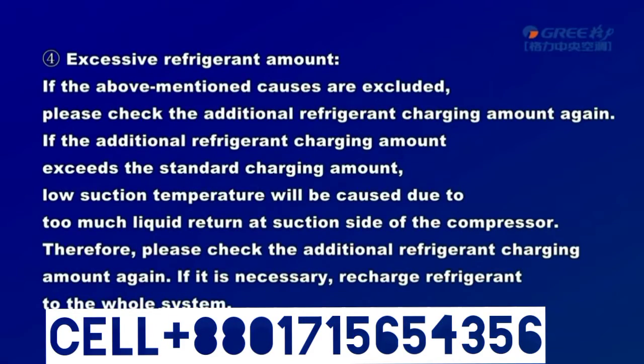4. Excessive refrigerant amount. If the above-mentioned causes are excluded, please check the additional refrigerant charging amount again. If the additional refrigerant charging amount exceeds the standard charging amount, low suction temperature will be caused due to too much liquid return at the suction side of the compressor. Therefore, please check the additional refrigerant charging amount again. If it is necessary, recharge the refrigerant to the whole system.